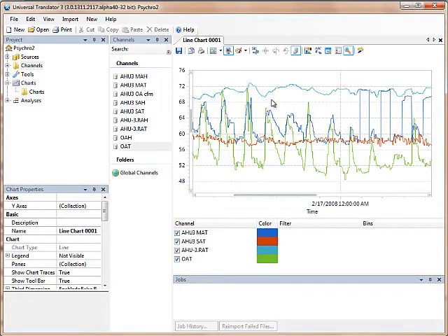And this is a 24/7 unit that has both temperature and humidity control. And here's the return air temperature, so the rooms are pretty steady at 68 to 70 degrees. But even at night, I can see that the air handler is cooling down. So it goes from this blue line, which is around 70 for return air, down to about 58 or so for supply air. So it's always cooling. In this half, it's using outside air, and so the economizer cycle is active at night. In this half of the picture, it's not active at night.